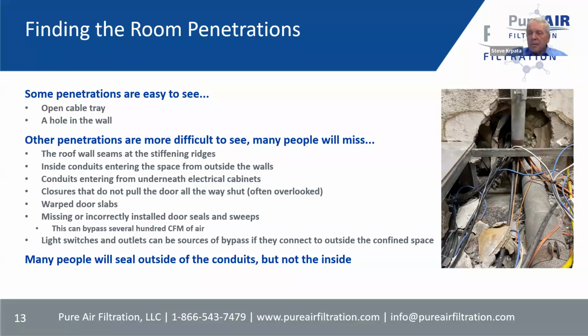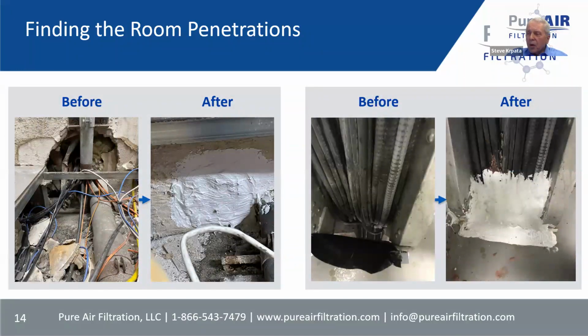Let's say light switches and outlets can be a problem, especially if there's sheetrock. Sheetrock rooms are terrible because they usually hide a lot of sins, and light switches and duplex outlets can be a way for outside air to bypass into the space. If they're surface mounted, it's not usually as big a deal. You don't have to worry about that so much. But in the other case, you do have to worry about switches and outlets. So these are some before and after photos of sealing different places. The one on the left was in the prior slide also.